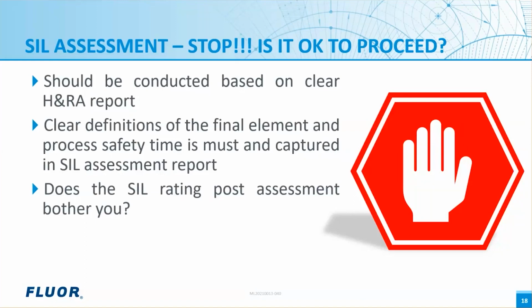Another critical aspect for SIL assessment is clear definition of the final elements and process safety time. Normally, a SIF has a primary action and secondary actions to operate additional final elements. The actuation of the primary element should be sufficient for mitigating the hazard, right? But what happens if all the final elements are listed as primary actions? The SIF will have an unrealistic final element voting. Can the SIL target be achieved with such a design? No, definitely not.